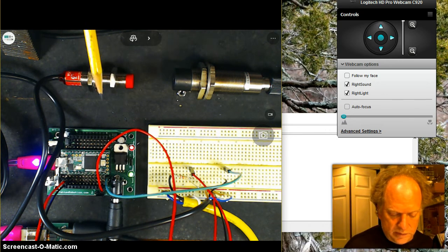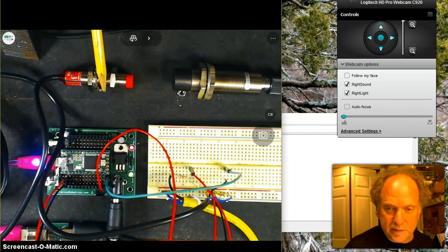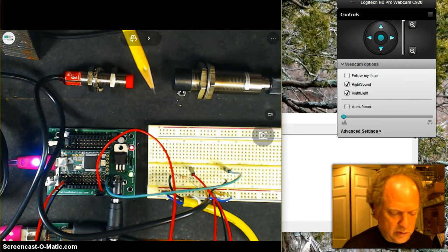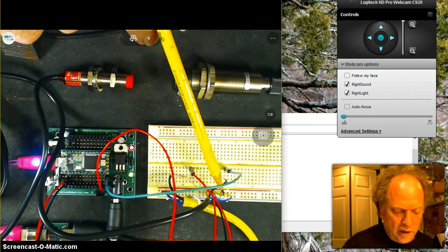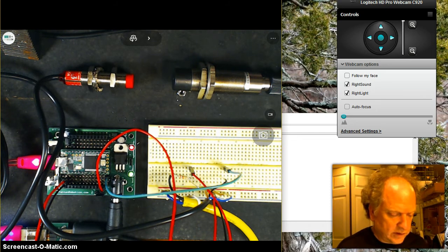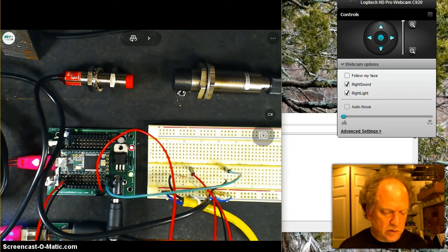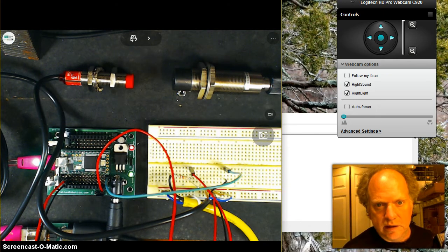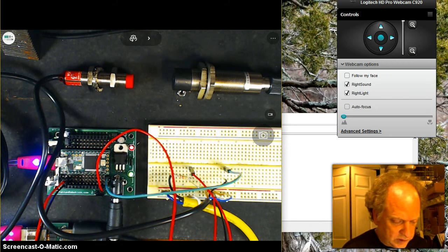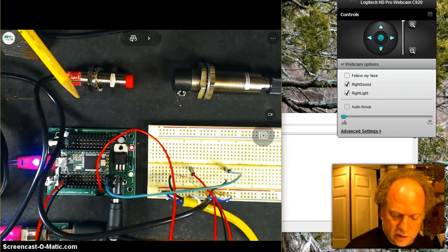In this case, we're going to be dealing mostly with this NPN device. NPN are sinking devices. So, in other words, the black signal wire from this particular device is simply going to be on or off to ground. So, if we have a source, it'll allow it to flow. No matter what the voltage is, it'll simply connect it to ground, which makes it really ideal for hooking up to digital sensors, and I'll explain that almost immediately. But first, I'm going to talk about their hookup.